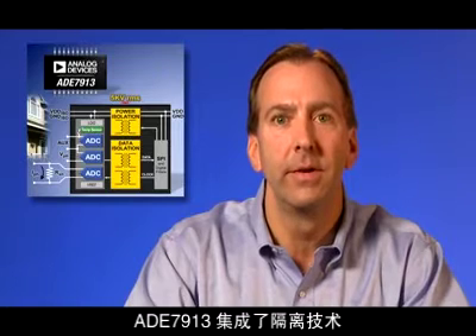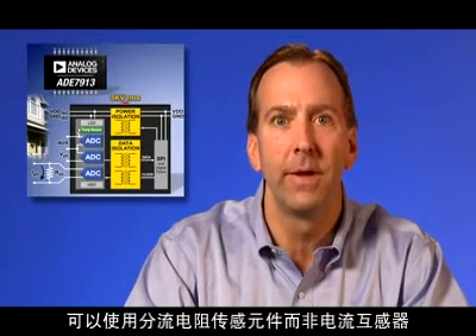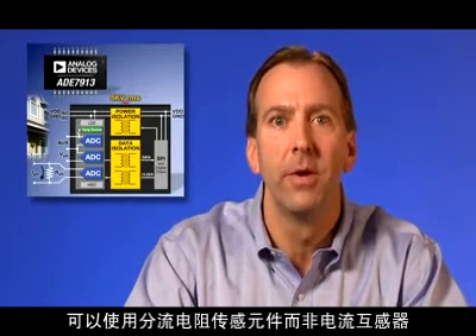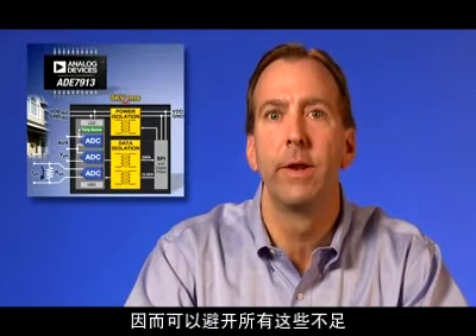This is especially true for DC-tolerant CTs, and also situations where additional shielding is needed to pass regulatory requirements. The ADE7913 has integrated isolation and enables the use of shunt resistor sensing elements instead of current transformers so that all of these drawbacks can be avoided.